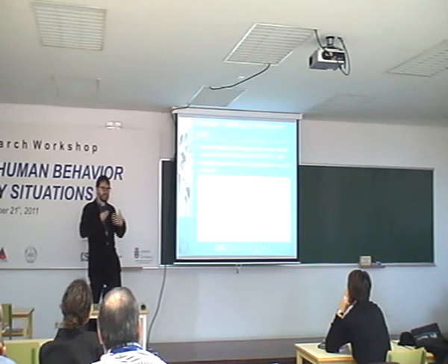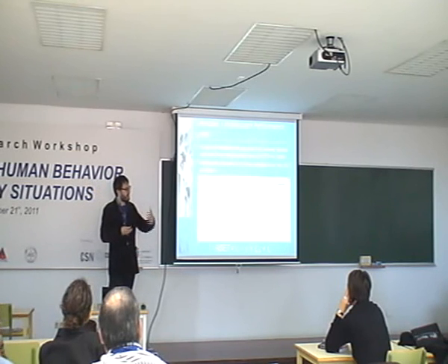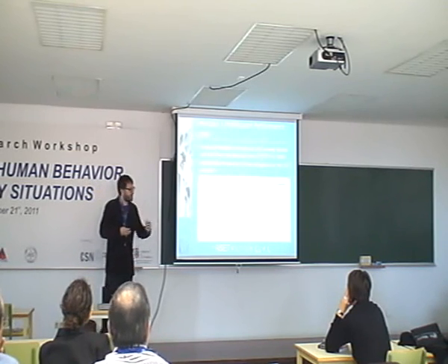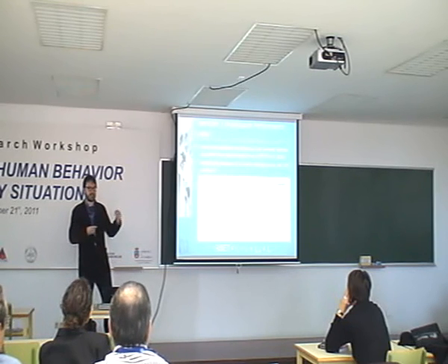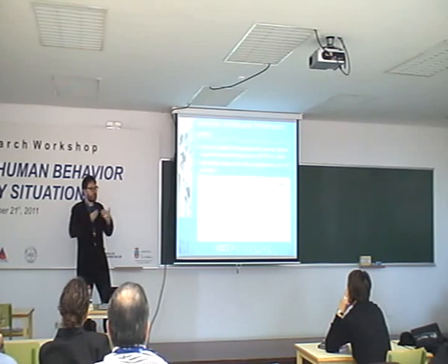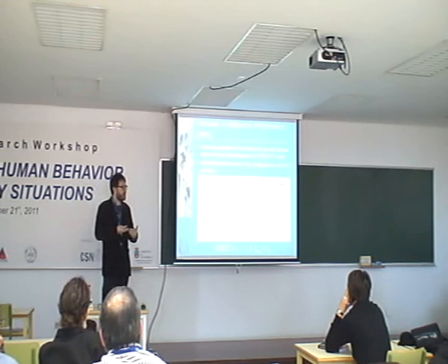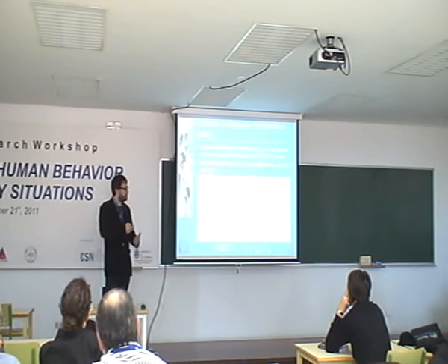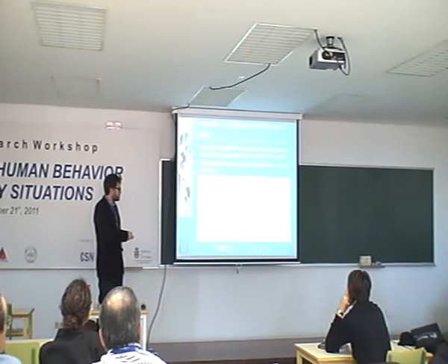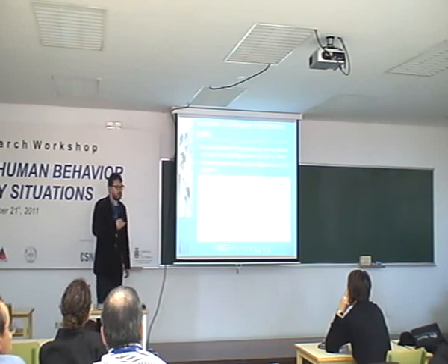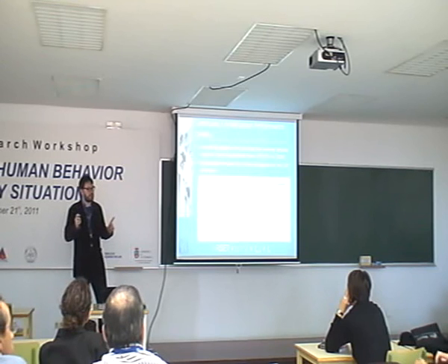However, when there's any staff activity required, when there's any confirmation required, or when the initial detection is by a member of staff, then the human process intervenes. And we can't then necessarily assume that the manufacturer's guidance is appropriate. In these situations, time to notification may be much greater than we had previously assumed.